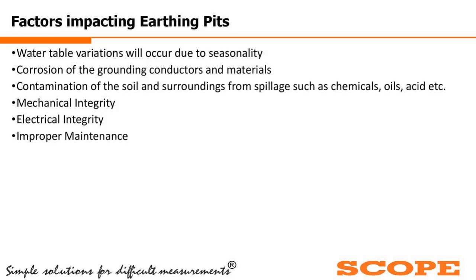Then comes the mechanical integrity and electrical integrity of the rod, as well as the associated nearby surface. And last but not least, if there is no proper maintenance, then anything will go bad. It is similarly applicable to earth pits: if we do not maintain the earth pit properly over a period of time, the pit resistance will change.